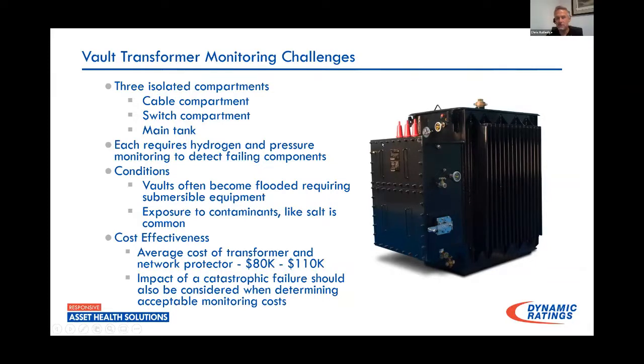And lastly on this, when considering the monitor, and this is something that we do a lot of, we've recently introduced some breaker monitoring into the market, and it's the same thought process. You really have to consider your reasons for putting a monitor on something, and it's not always directly related to how much the piece of equipment cost. With these, it's a huge safety problem, and it's a logistic nightmare to change them out. I mean, it's cranes shutting down streets to get in vaults. The same with breakers. I see a $2 million transformer, nobody bats an eye at putting $100,000 worth of monitoring on that transformer, and yet you look to the right and there's a high side breaker protecting that transformer. That is the main means of protection for the transformer, and it was installed in the 50s. And there's nothing looking at it.